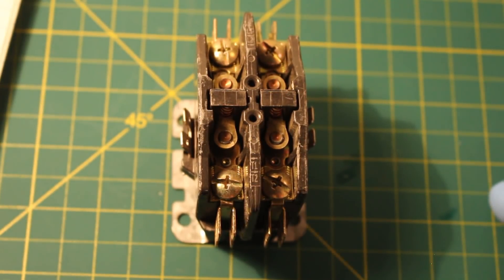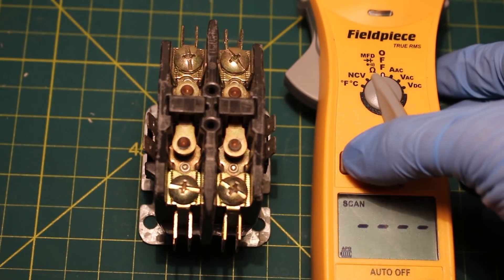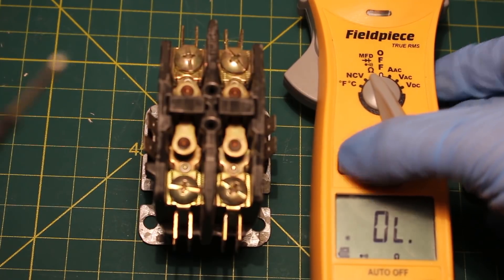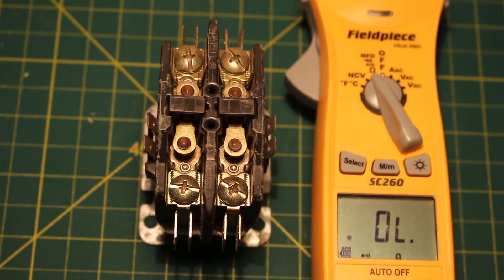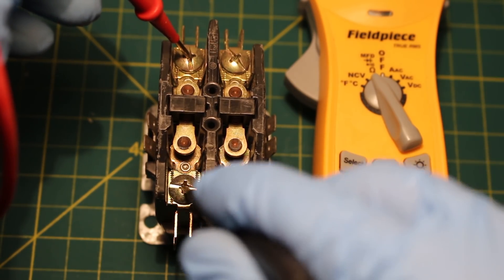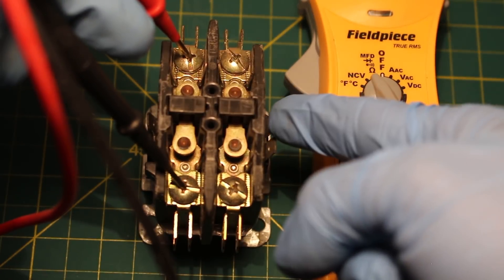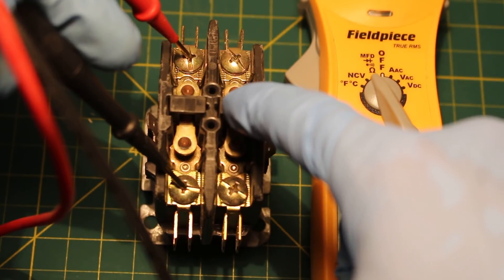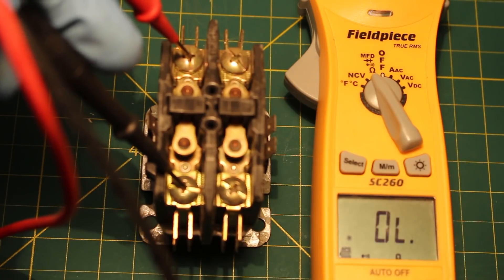And I will prove this to you using a multimeter. I have my meter out and I'm going to set it to continuity. Once we've selected that, we're going to short our leads to make sure the meter works. I'm going to put one lead on the line side and one lead on the same pole on the load side. So when the thermostat calls for cooling, it will energize your coil and close these contacts, sending power from your line side to your load, thus energizing your compressor. There's no continuity — and there's proof for you guys.